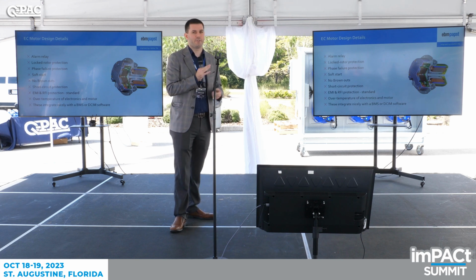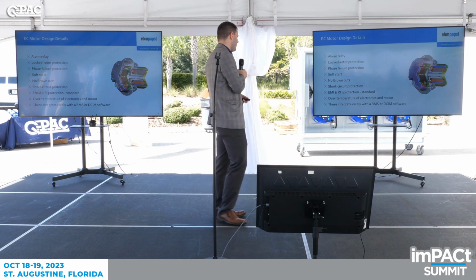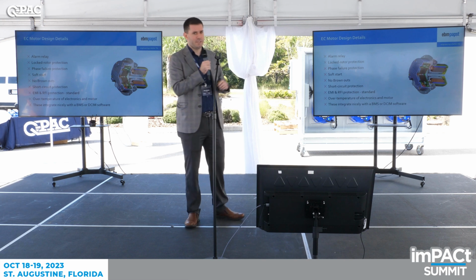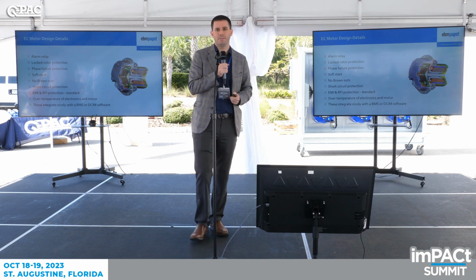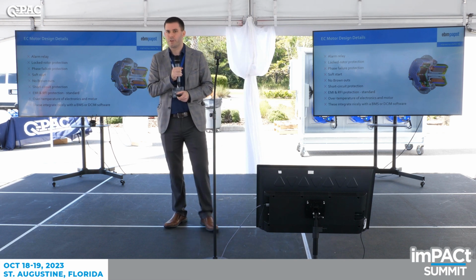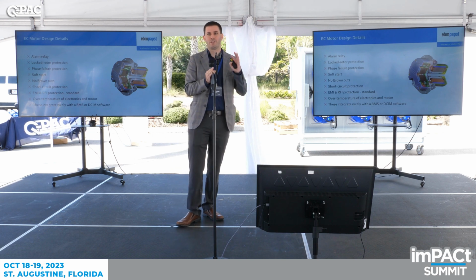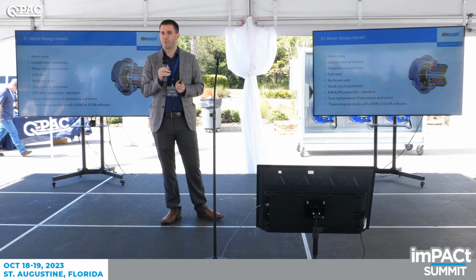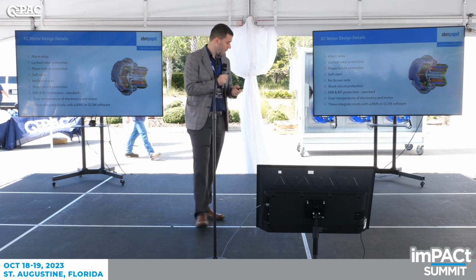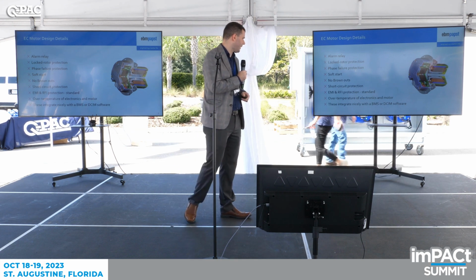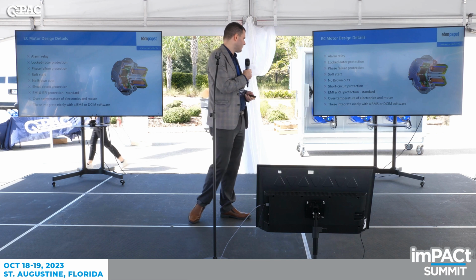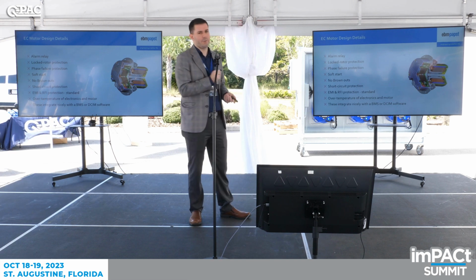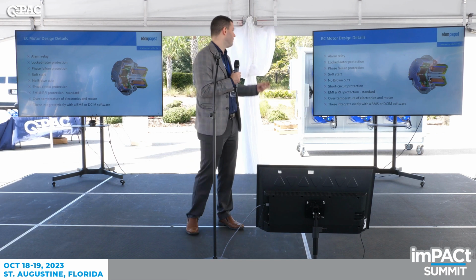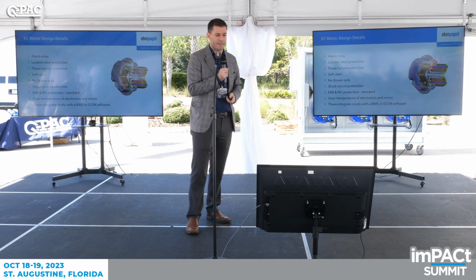So with the EC motor, you never generate that extra power. It has soft start, no brownouts, short circuit protection. There's no SCCR rating needed with an EC motor, because there's no wiring between the control electronics and the actual motor itself. You don't need to worry about SCCR. EMI, RFI protection standard, over temperature of the electronics in the motor standard, and they integrate very nicely with the BMS, DCIM, with that single point contact that Q-PAC has.